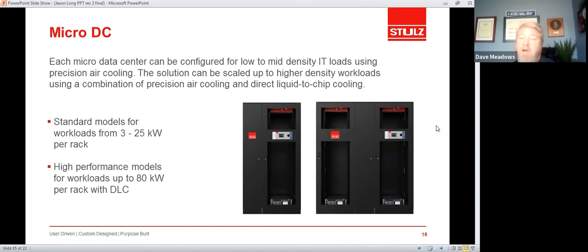And this technology is our direct liquid to chip systems. Many of the server manufacturers are making liquid cooled servers these days, and we can provide up to 80 kW of cooling in that module. Typically, you would only see these really high watt density applications in high performance computing labs, such as a university, or maybe a cryptocurrency mining operation.